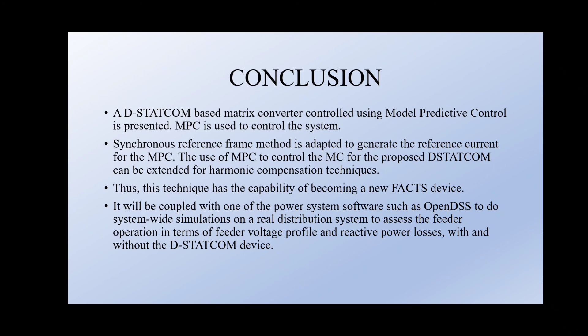It will be coupled with one of the major power system software packages such as OpenDSS to do system-wide simulation on a real distribution system, to assess the feeder operation in terms of feeder voltage profile and reactive power losses with and without the D-STATCOM devices.